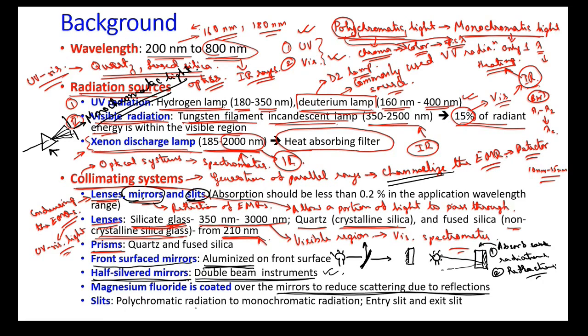Slits convert polychromatic radiation to monochromatic radiation, as already discussed, and there can be two types: entry slit and exit slit. An important point is that whatever glasses are used — lenses, mirrors, or slits — the absorption should be less than 0.2% in the application wavelength range, meaning these must be very high-quality glasses.